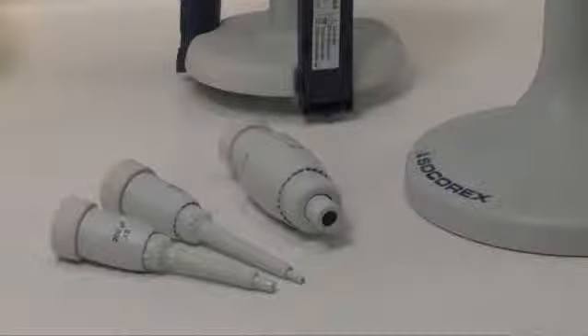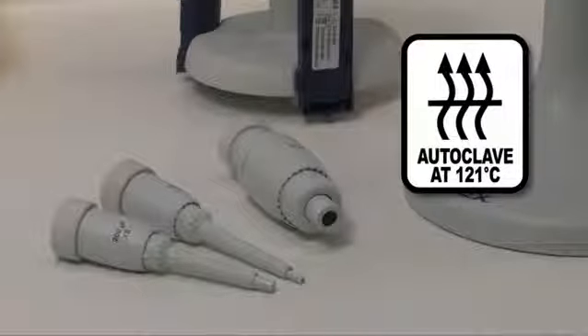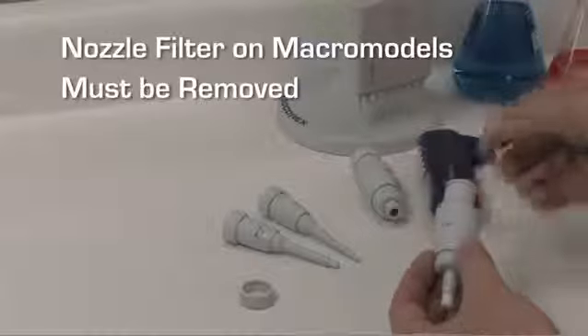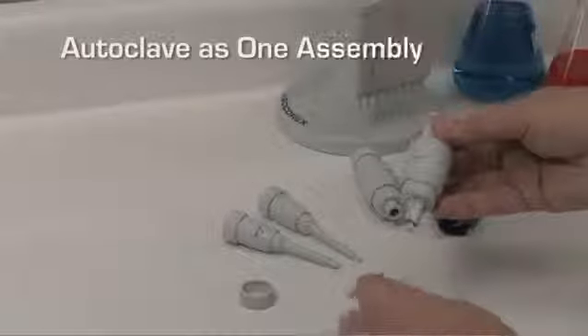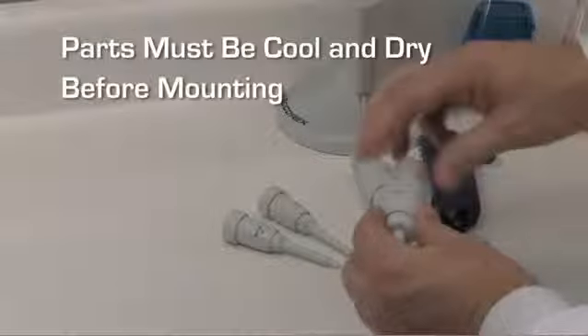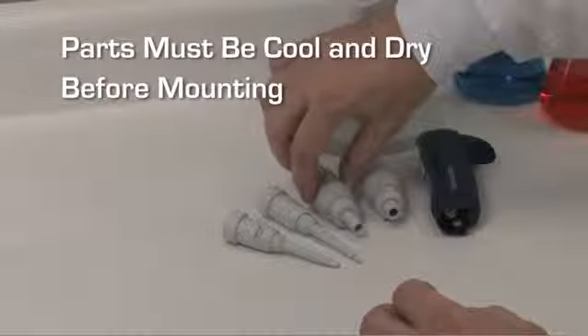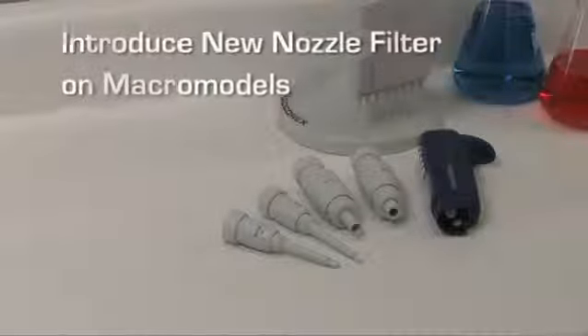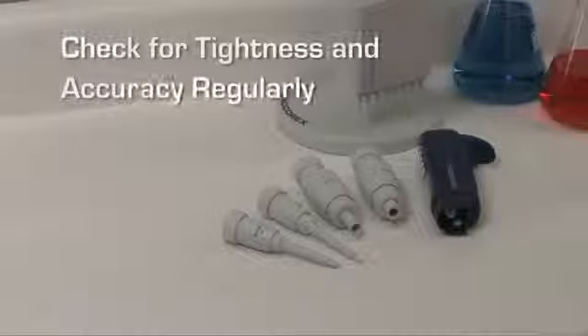Only the volumetric module is autoclavable at 121 degrees Celsius, 250 degrees Fahrenheit, and it must be disassembled from the control unit. The nozzle filter on macro models must be removed. Autoclave a volumetric module as one assembly. Parts must be cooled down and completely dry before mounting on a control unit. Introduce a new nozzle filter on macro models. Check for tightness and accuracy after the first cycle, then regularly, but at least after 50 autoclaving cycles.